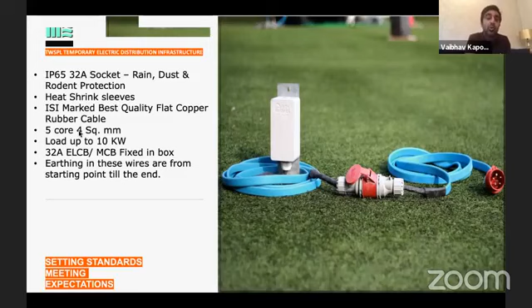Let's cut down one thing in between. I'm not using a 4 square mm cable; I'm using a 2.5 square mm cable. So what happens? The MCB can take a load of 10 kilowatts. The socket can take a load of 10 kilowatts, but the wire can't. So the wire will start getting heated up. In the other case, if the socket is less, then the socket will fail. So the whole chain of electricity has to be maintained from the start till the end.